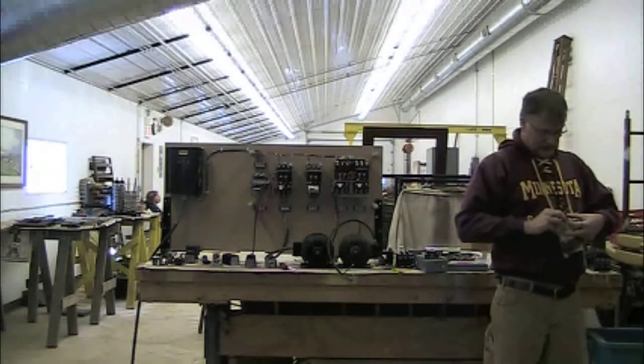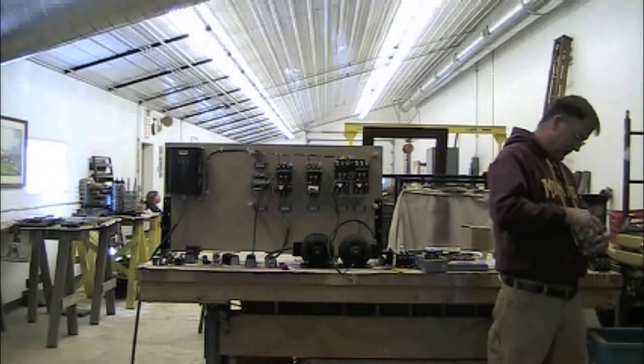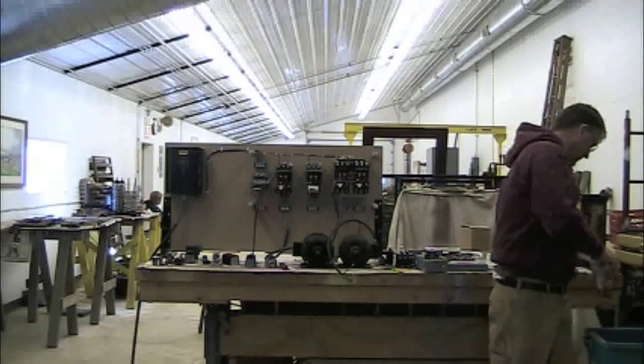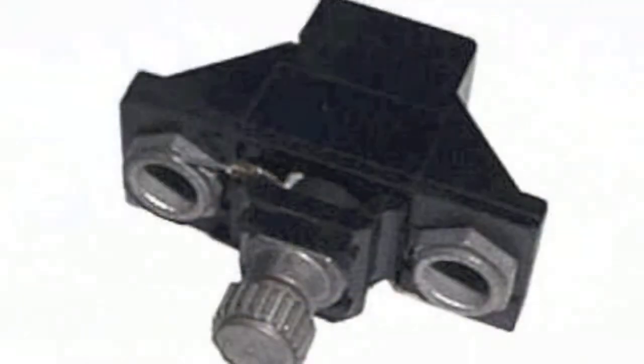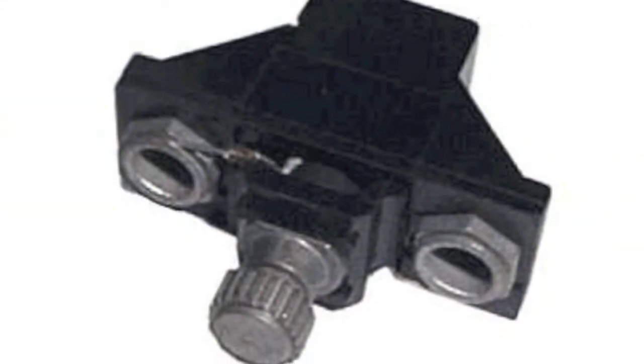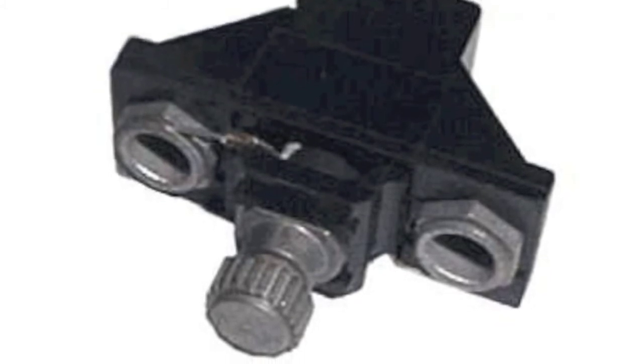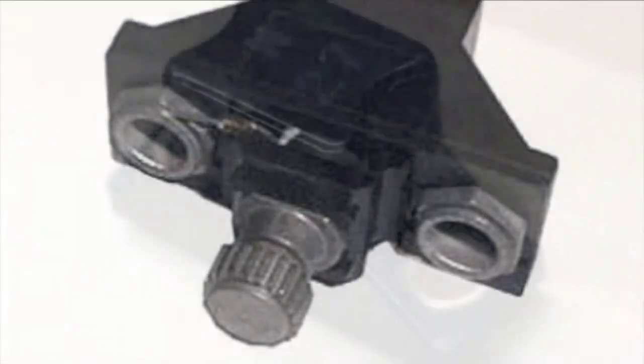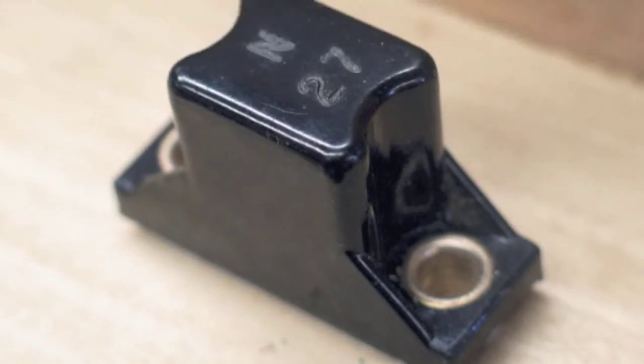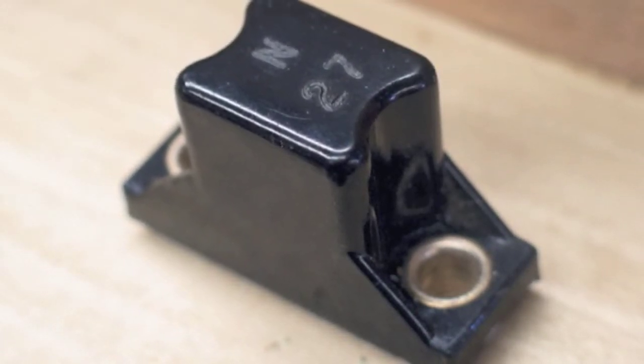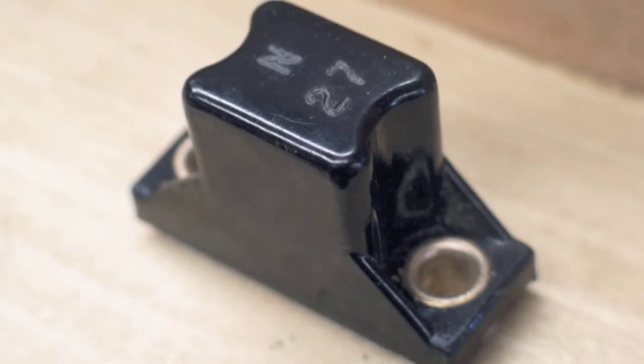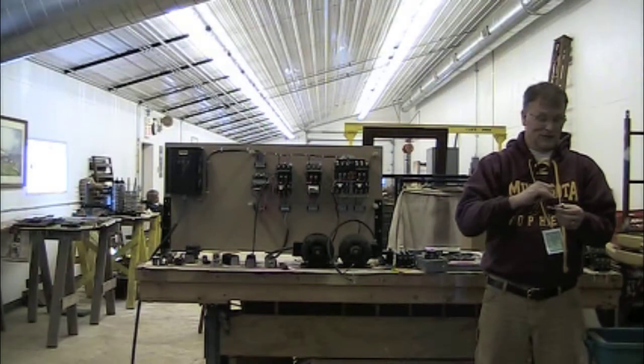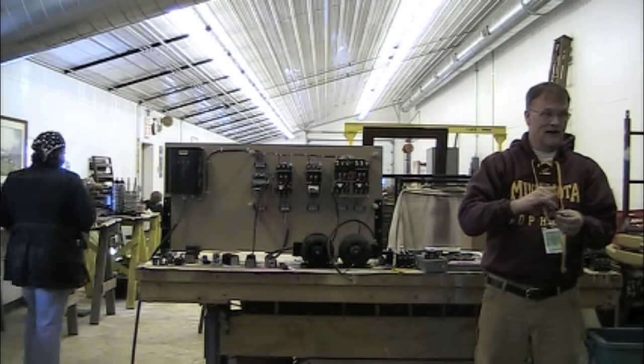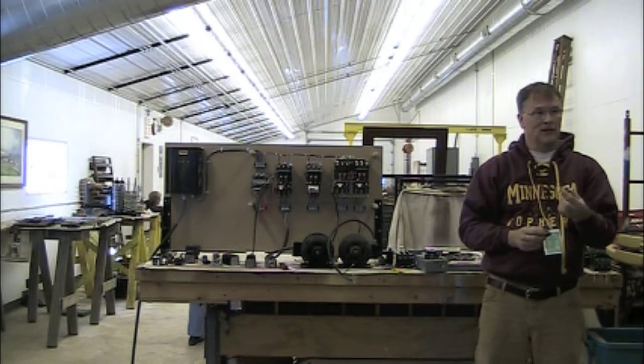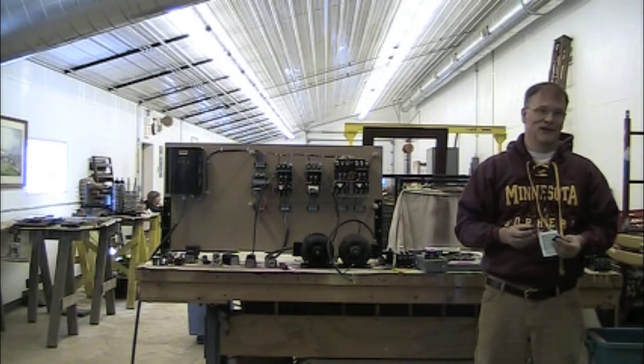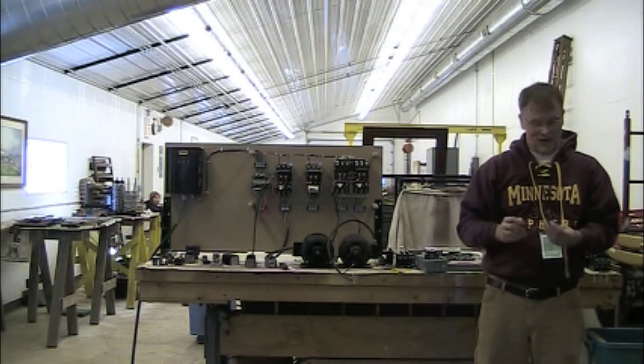And the only difference between the N's and the W's is the spindle is built into the W, and the N is just the heater element. So this part is actually part of the overload relay on the older types. So if you have any 709s that are Series K or later, the last part of the lifetime of them, you can actually remove the spindle off of the overload block and replace it with a Type W heater. And then there's a whole other chart of heater values that go with that for when it's used in those type.